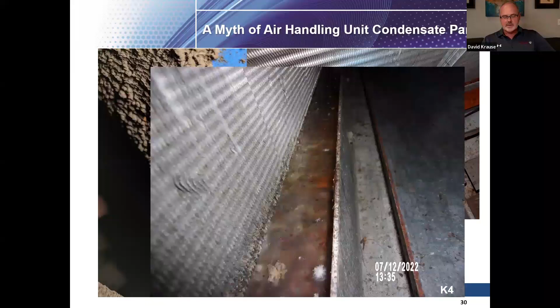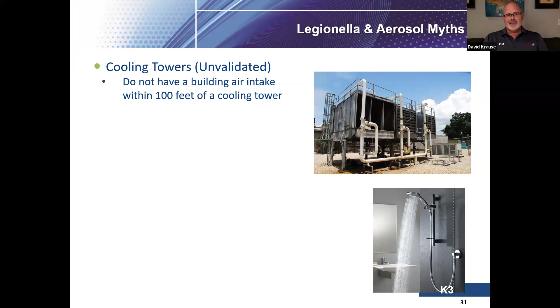Again, aerosol sources, cooling tower remediations, and recommendations of 100 feet for a cooling tower. I don't know any basis for this. Often cooling towers cause outbreaks in communities—they're community-wide, widespread, affecting people who aren't even in the building where the cooling tower is present. So why 100 feet? Often we see there's really no detectable aerosol in the area close to the cooling tower, because it acts more like an umbrella effect. Where did the 100 feet come from? I have no idea if that has any basis. I've never seen any evidence for that.